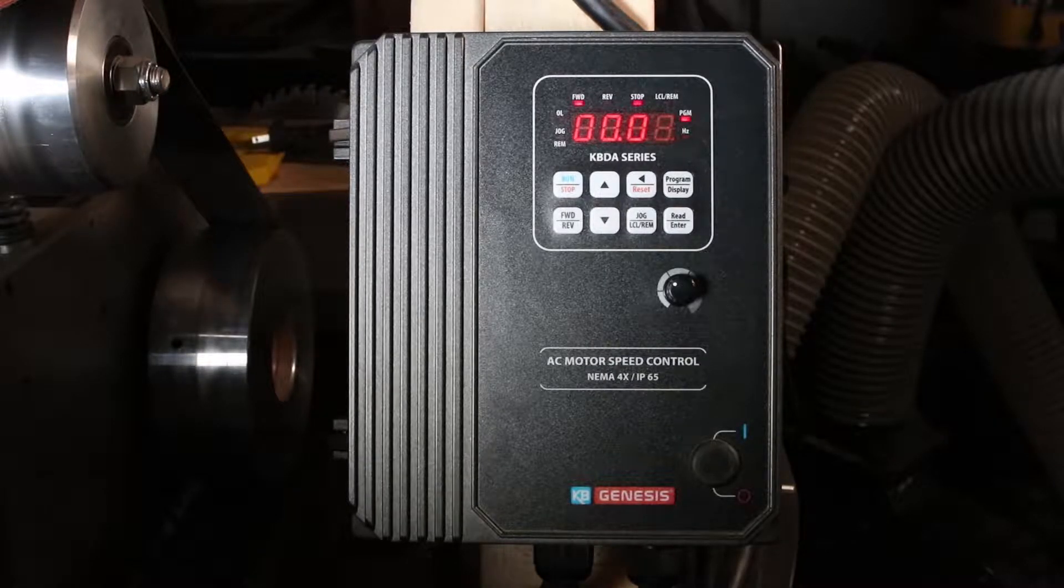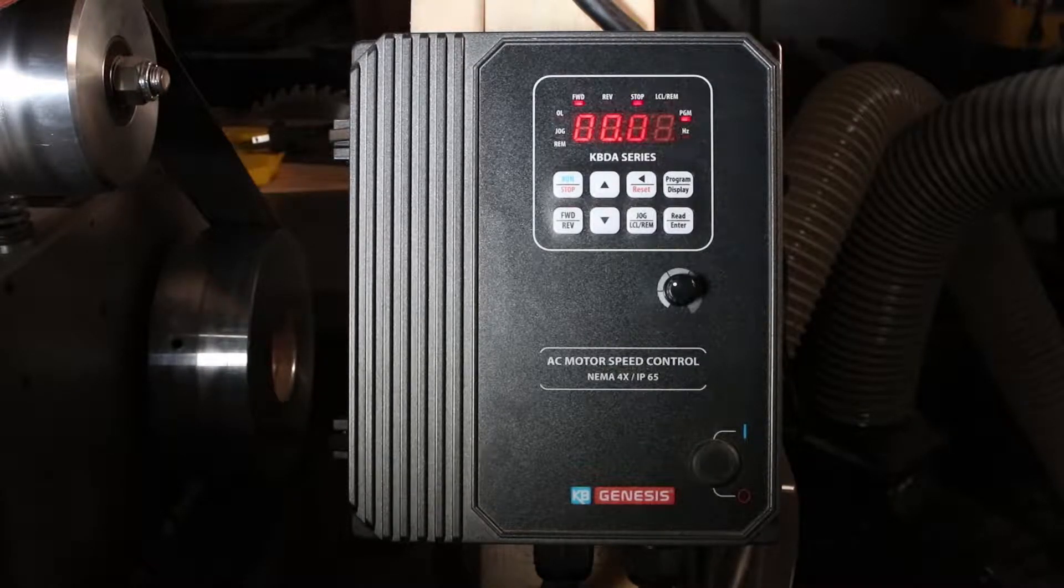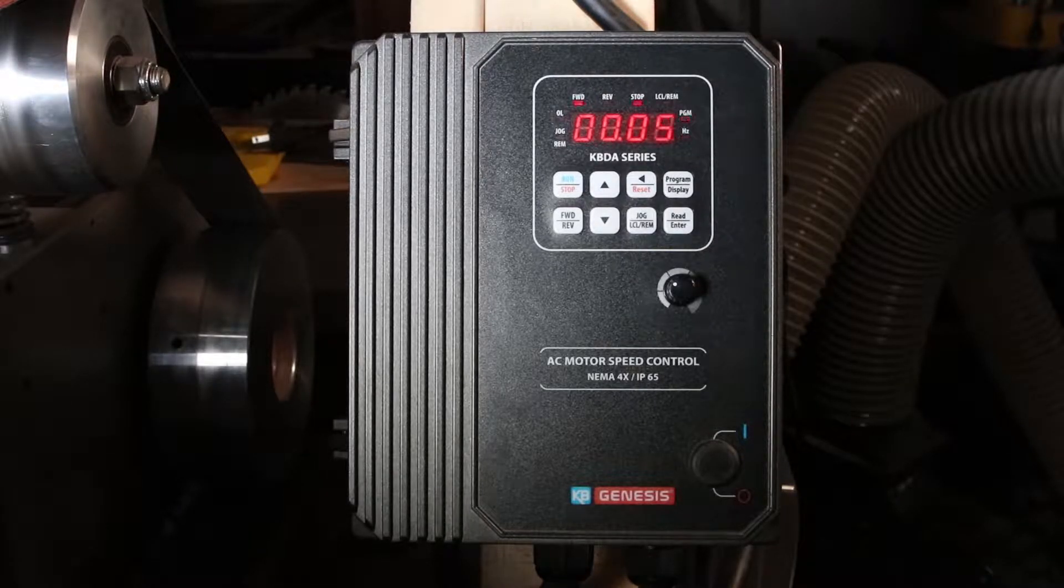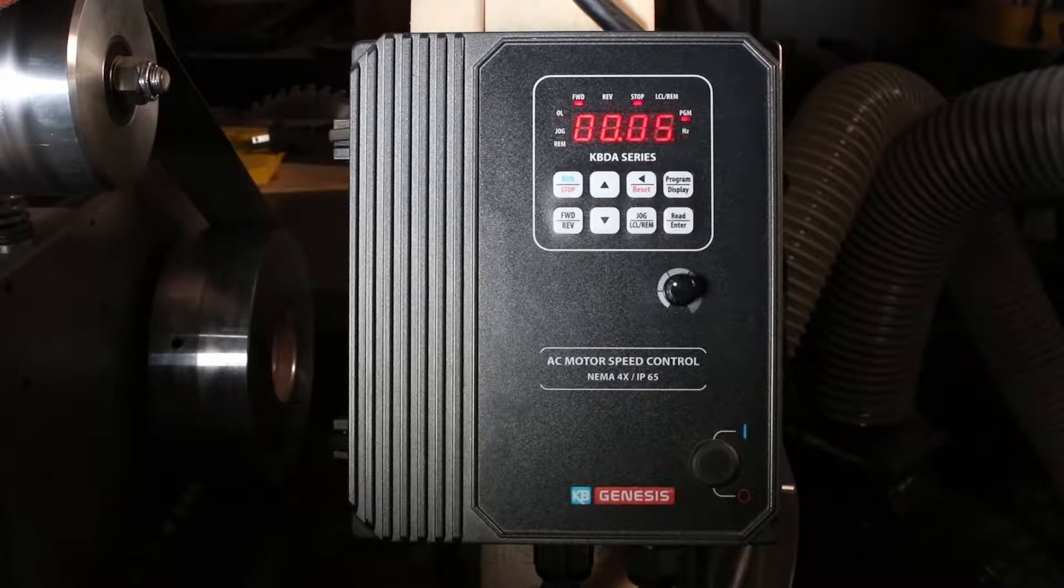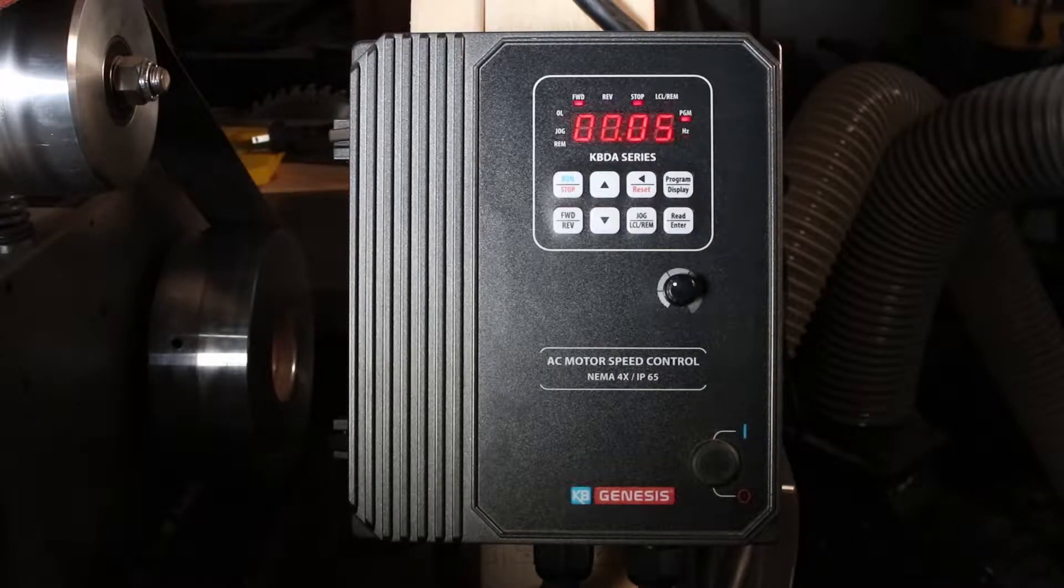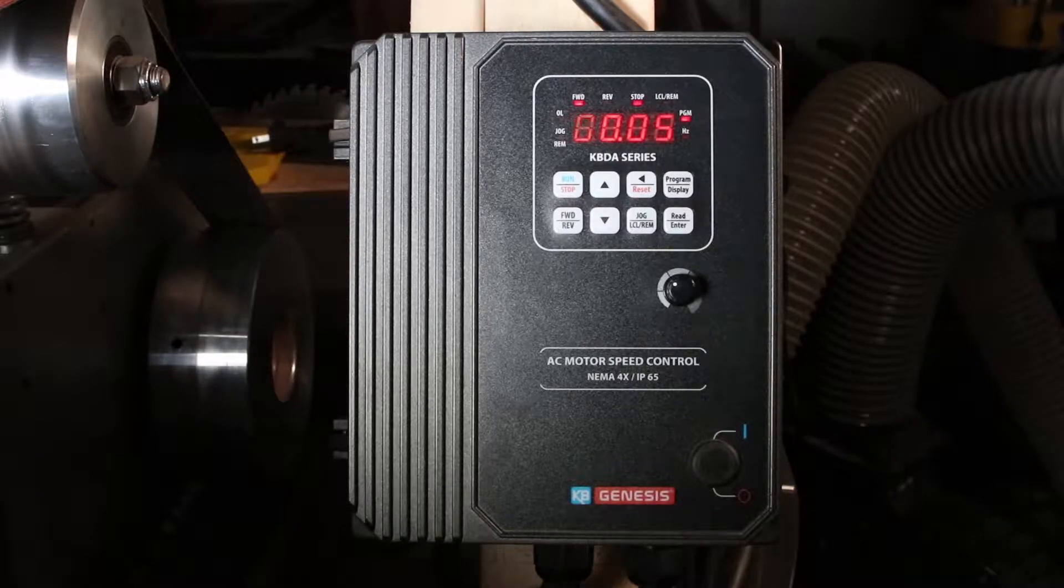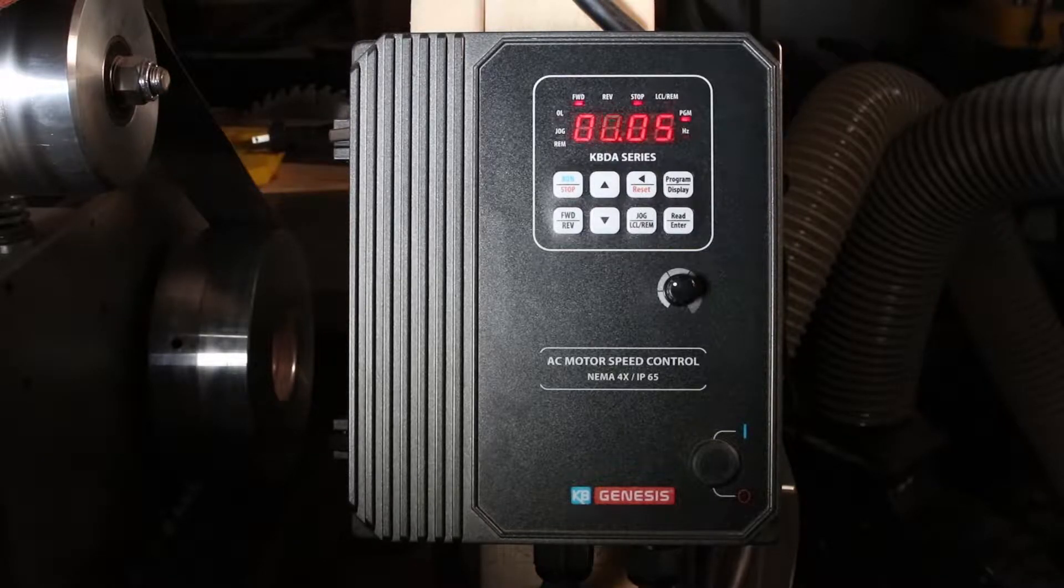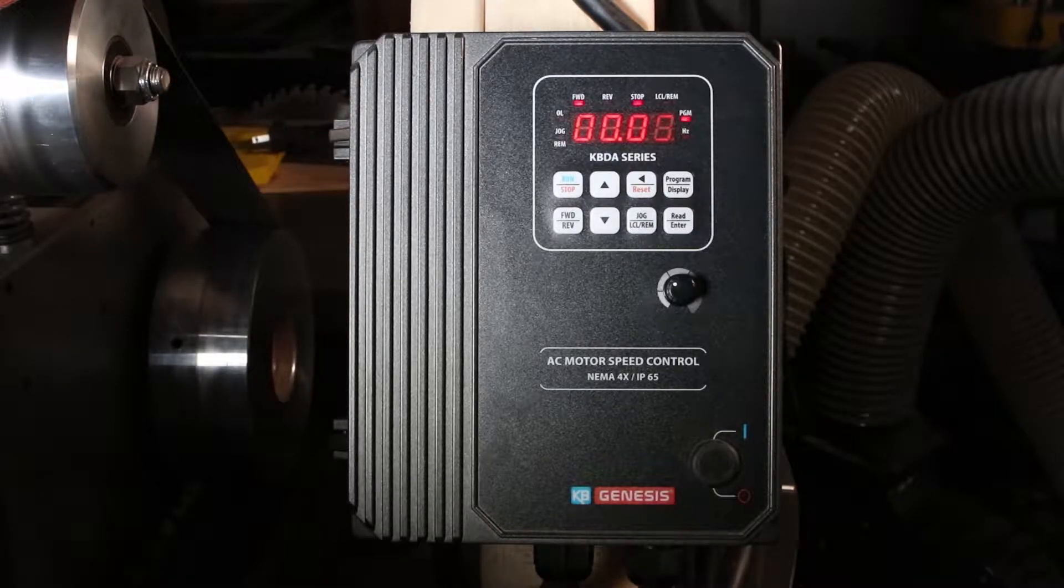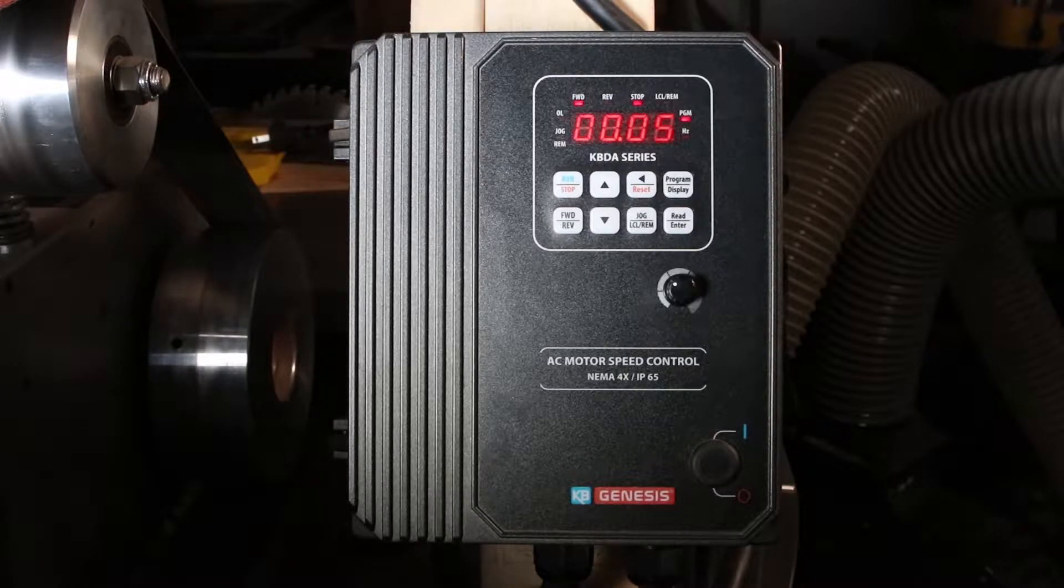Now one thing to keep in mind when you run the motor at twice the frequency is this: once you are over the standard 60 Hertz, the torque of the motor will drop inversely proportional to the speed.